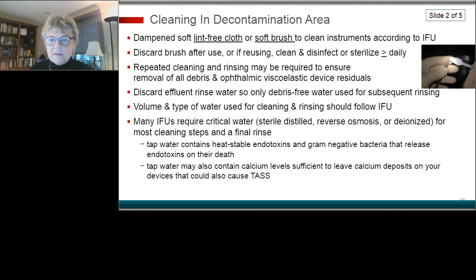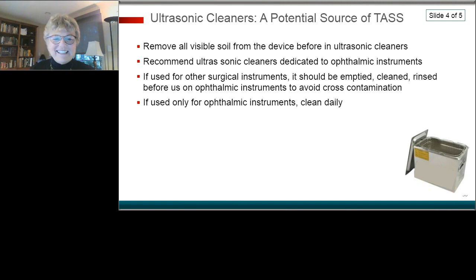Ultrasonic cleaners. Okay, this is a really important part. Remove all the visible soil from the device before use in the ultrasonic cleaners. Recommend ultrasonic cleaners dedicated to ophthalmic instruments. And you don't need a huge one. You can use a small one, so it's not a huge expense. But being dedicated to ophthalmics, I think, makes a huge difference in several of the complications that can occur. If used for surgical instruments in addition to ophthalmic equipment, it should be emptied, cleaned, and rinsed before ophthalmic instruments to avoid cross-contamination. If used only for ophthalmic instruments, it should be cleaned daily.